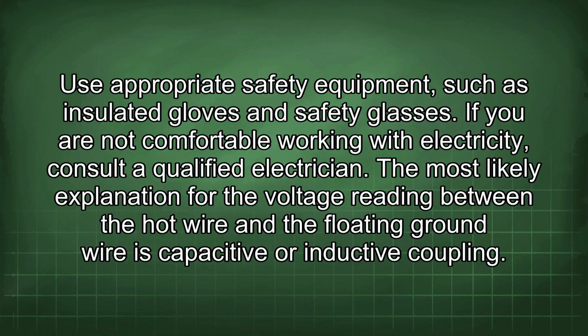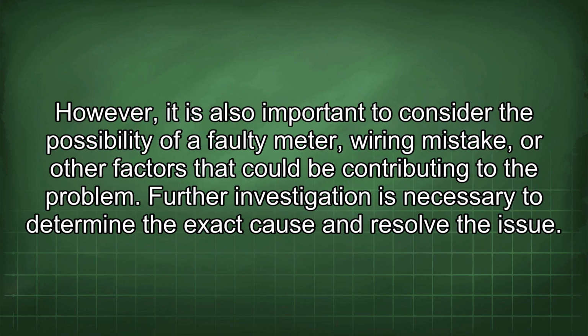The most likely explanation for the voltage reading between the hot wire and the floating ground wire is capacitive or inductive coupling. However, it is also important to consider the possibility of a faulty meter, wiring mistake, or other factors that could be contributing to the problem. Further investigation is necessary to determine the exact cause and resolve the issue.